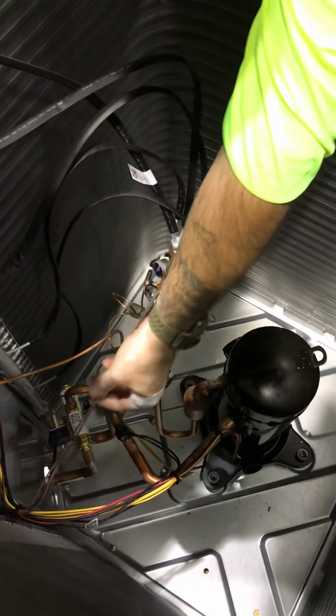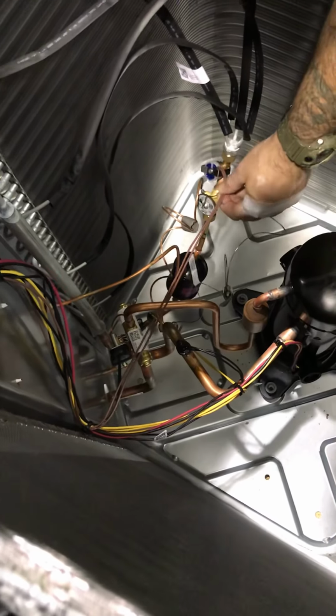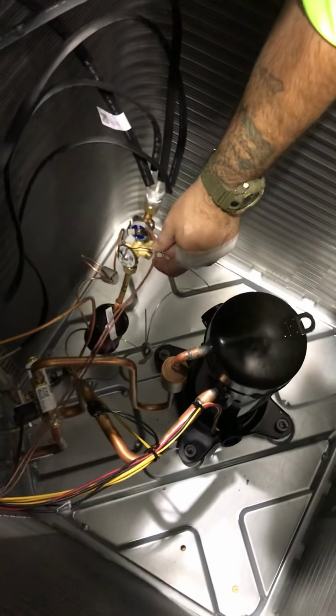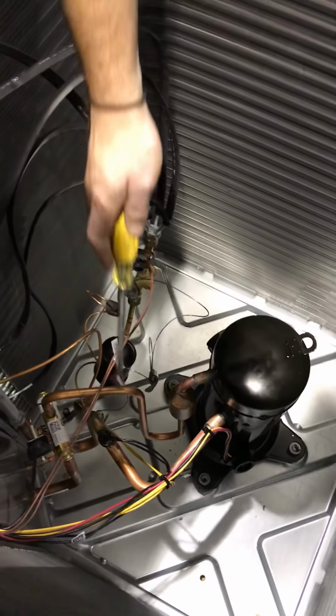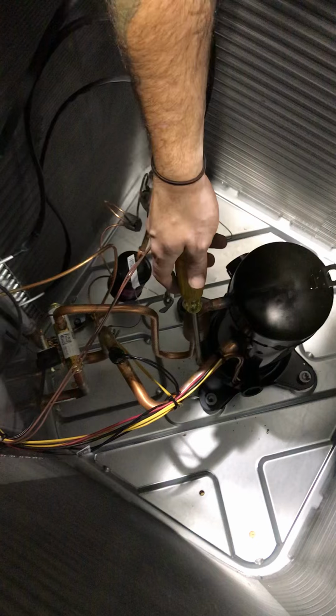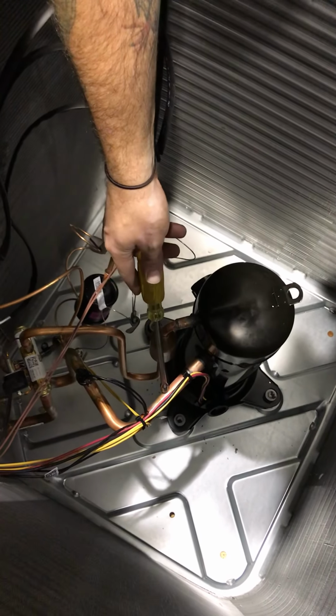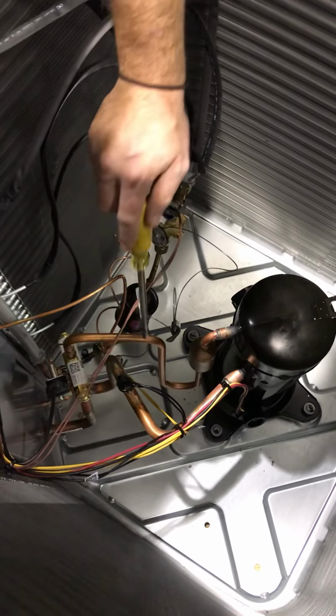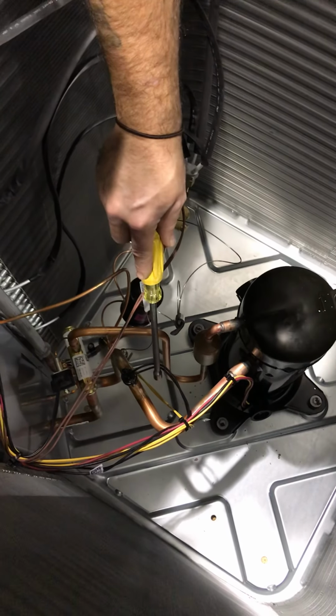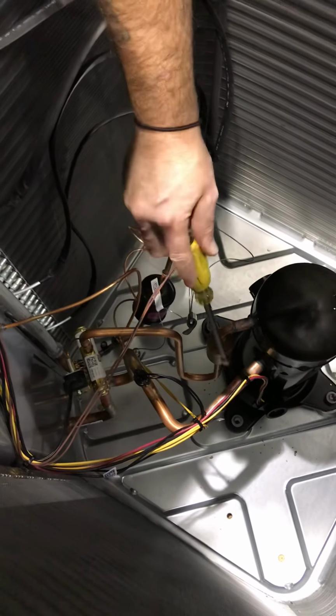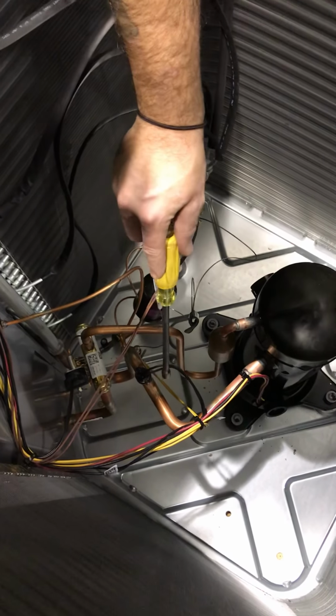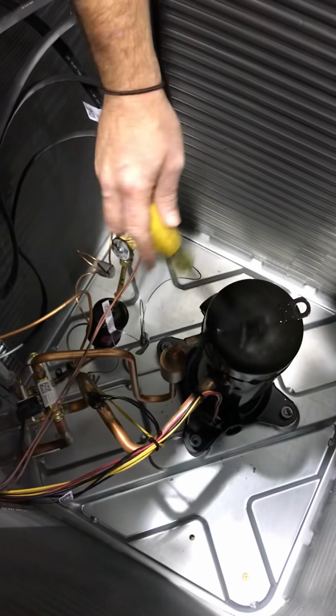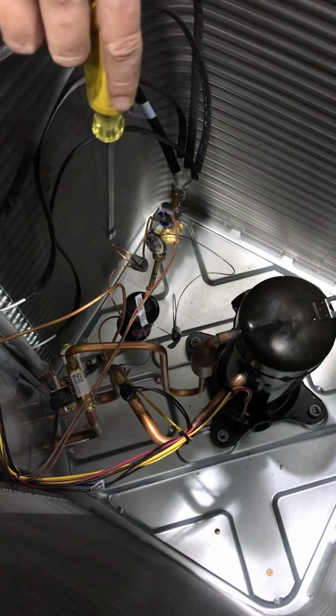All right, two wires go to your defrost board. Coil sensor. All right, guys. It's either going to be here or it's going to be connected to this for temperature. Okay. This is your transducer. This is on your suction line. So suction is low pressure. Liquid is high pressure. This is a low pressure transducer, which lets you know how much pressure is moving through here. If it's too high, then it's going to send a signal to my defrost board, which is going to turn my unit off. That's what transducers do. That's a low pressure transducer.